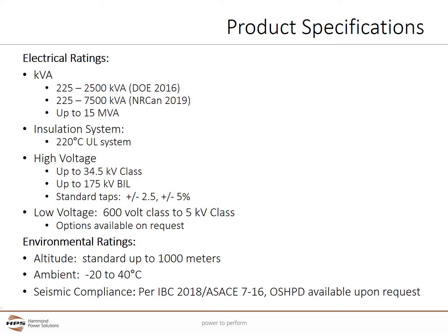Typical product specifications include meeting U.S. DOE 2016 efficiency regulations up to 2,500 kVA and Canadian NRCan 2019 regulations up to 7,500 kVA. The Millennium E is available in higher kVA. The Millennium E's 220 degrees C UL listed insulation system uses VPI construction. Units can be built up to 34.5 kV class and 175 kV BIL. Standard full capacity taps are provided at plus and minus 2.5% and plus and minus 5%. Typical secondary voltages include 600 volt class to 5 kV class. Environmental ratings include altitudes standard up to 1,000 meters with higher altitudes available as specified, and standard ambient temperature ranges from minus 20 degrees C to 40 degrees C with much higher temperatures available if needed.